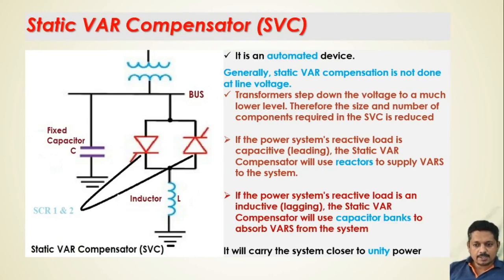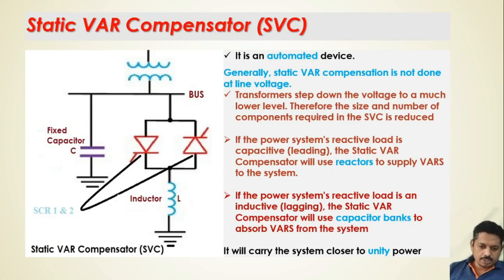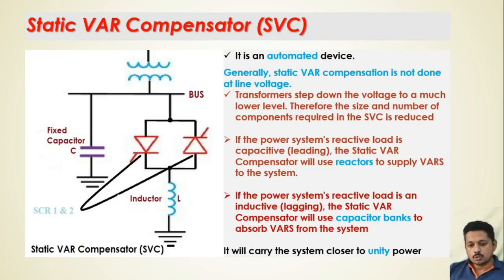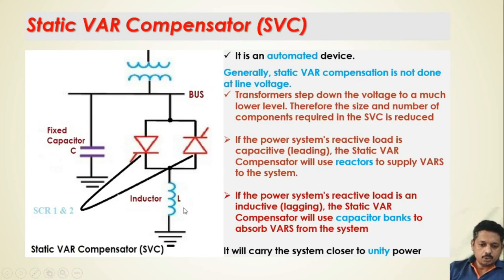Generally, a static VAR compensator is not operated at line voltage because it requires very high capacity switching devices, and high-capacity electronic devices are very costly. So we reduce the voltage to a usable form with a transformer, then use an SCR bank for switching purposes.